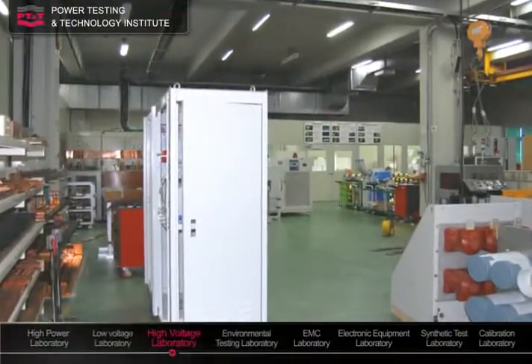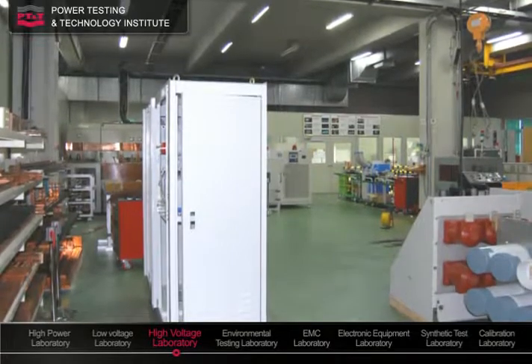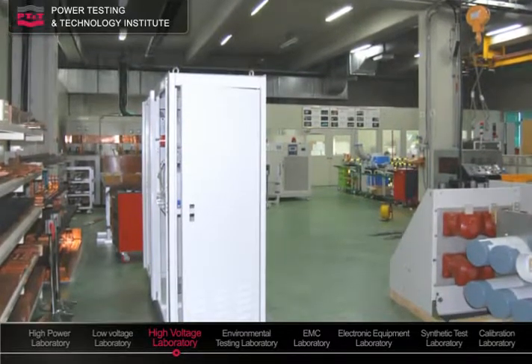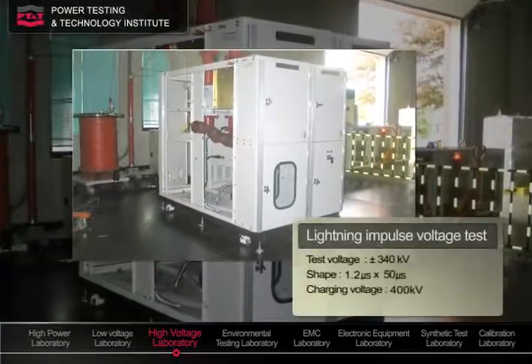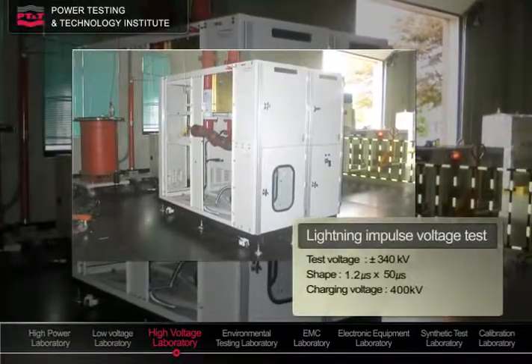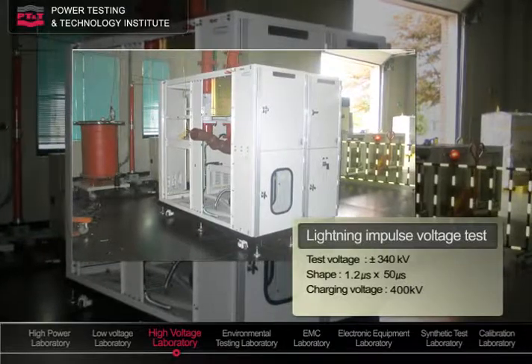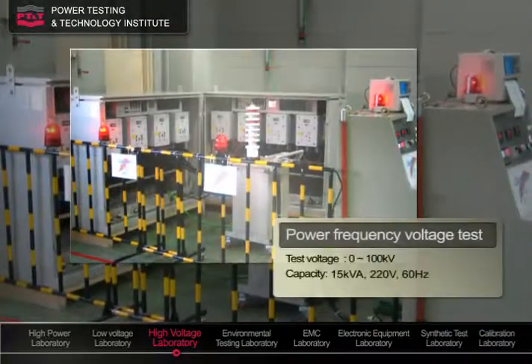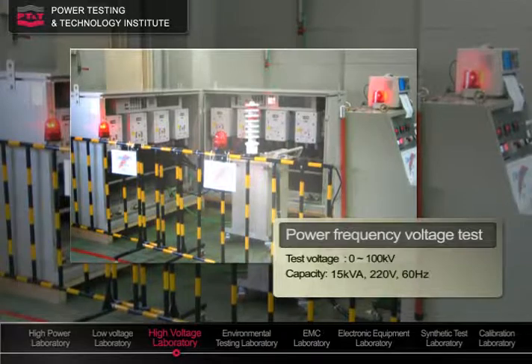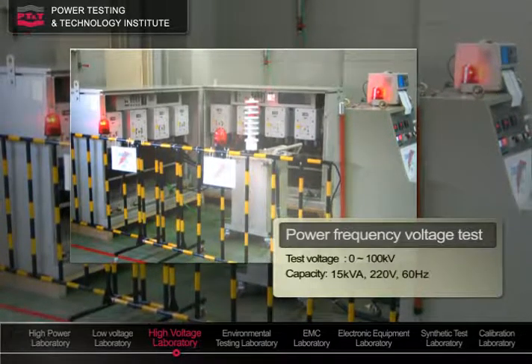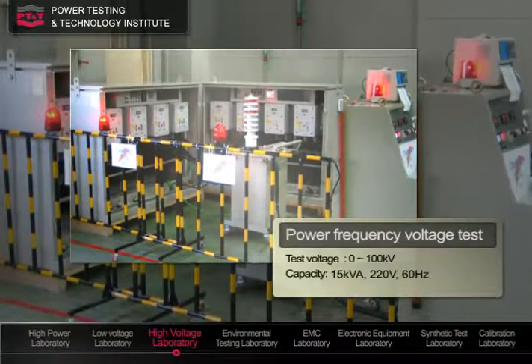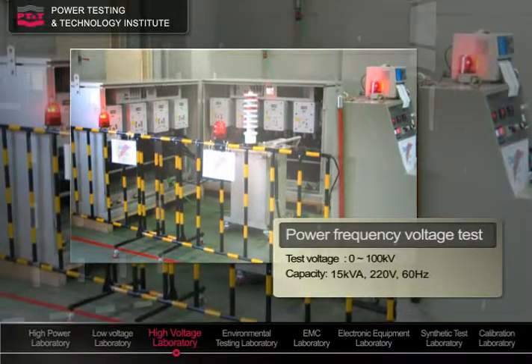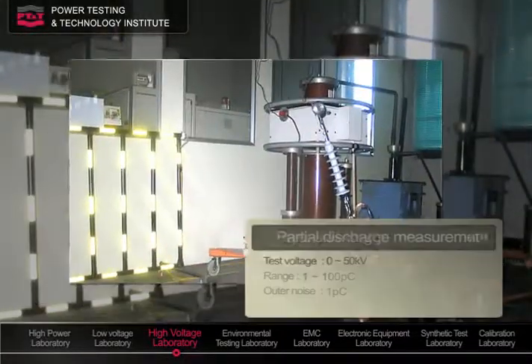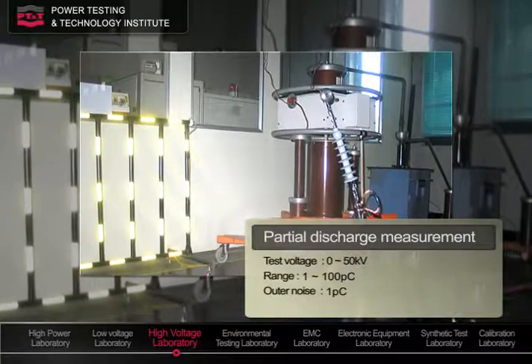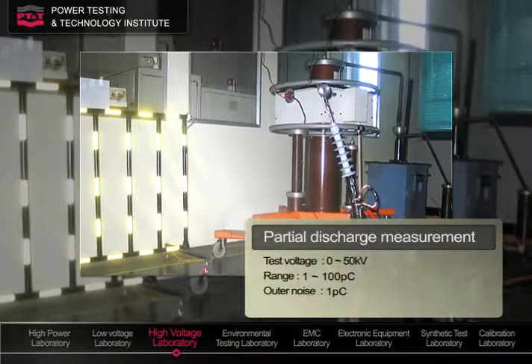High Voltage Laboratory verifies the electrical insulation performances of high voltage breakers and switches operating at the voltage higher than 1000 volts through lightning impulse voltage tests. In addition, abnormal voltage that might occur in ordinary operation is simulated with power frequency withstand voltage test, and internal insulation failures are tested with partial discharge tests.